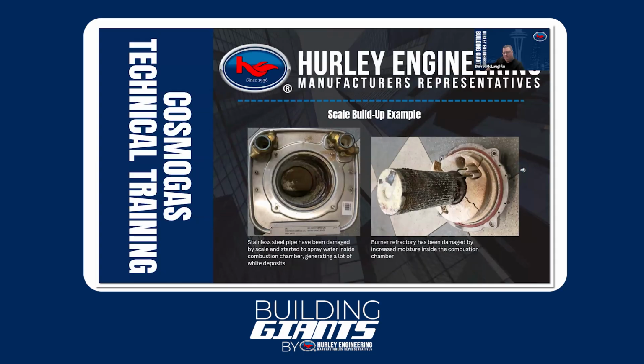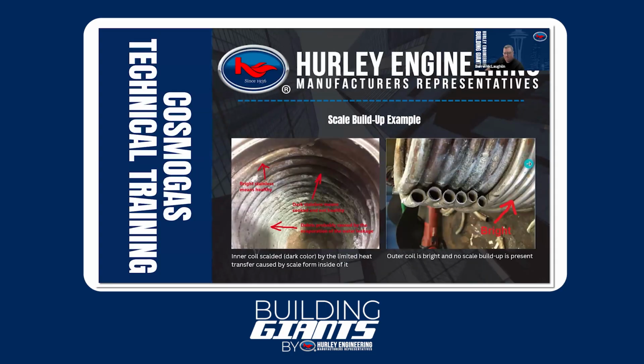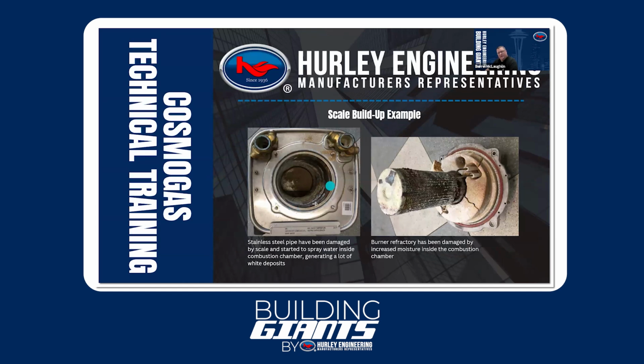However, the minute that metal starts getting dark, here you can see it. If you don't clean it off enough and your metal gets dark like this, as opposed to shiny, this is when you've damaged the heat exchanger. Our metal should always be able to be made shiny. If it's gotten dark, then we've overheated, we've overtempered it, we've done things we shouldn't do. So keep that in mind: the darker you're getting inside out, if you can't get it shiny, there's an issue. And then again, same thing with this burner. It doesn't look as dark, but you can see how it's warped, it's malformed on the end here. We've got cracks in the refractory. So that's an example of things you'd want to correct and replace.